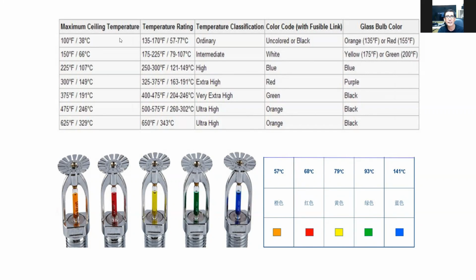As you can see, the ceiling temperature for uncolored black is about 38 degrees centigrade. This is about the temperature of a person that has fever. If it is white, it's about 66 degrees centigrade. This is the intermediate fire sprinkler system, which we commonly use. The high, the very high or the extra high is usually used in kitchens. And the ultra high is used in extreme temperature areas.